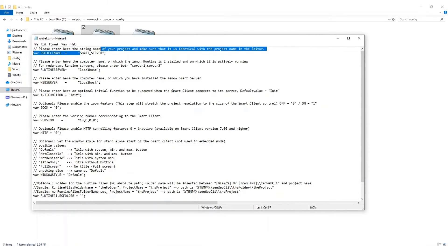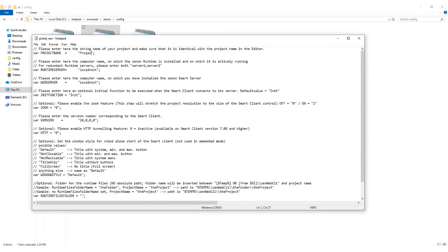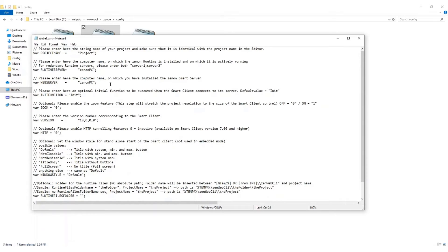The project's name must be entered under Project Name, and since I am running the Service Engine and the Smart Server on the same machine, I will enter that hostname under both Runtime Server and Web Server. Make sure that you use the hostname, as an IP address is not accepted by the Smart Server.